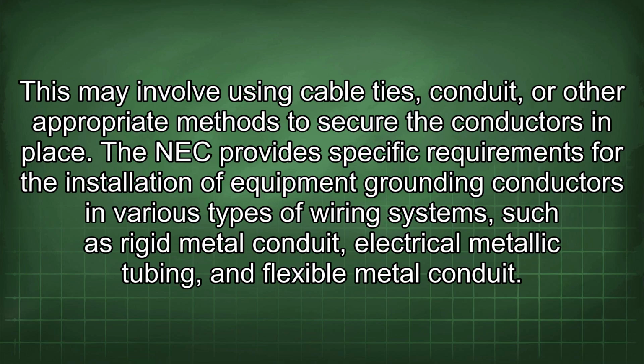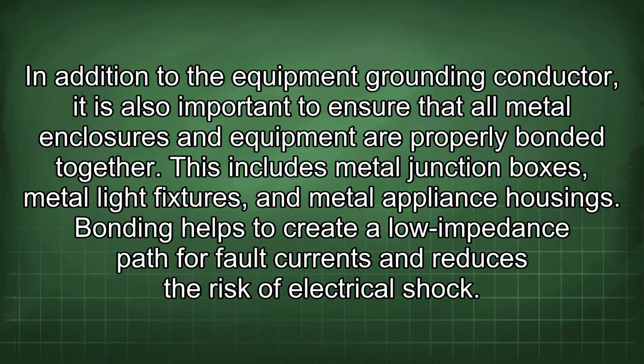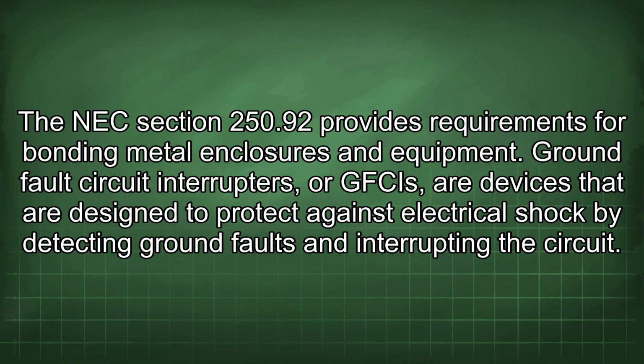The NEC provides specific requirements for the installation of equipment grounding conductors in various types of wiring systems such as rigid metal conduit, electrical metallic tubing, and flexible metal conduit. In addition to the equipment grounding conductor, it is also important to ensure that all metal enclosures and equipment are properly bonded together. This includes metal junction boxes, metal light fixtures, and metal appliance housings. Bonding helps to create a low impedance path for fault currents and reduces the risk of electrical shock. The NEC section 250.92 provides requirements for bonding metal enclosures and equipment. Ground fault circuit interrupters, or GFCIs, are devices that are designed to protect against electrical shock by detecting ground faults and interrupting the circuit.